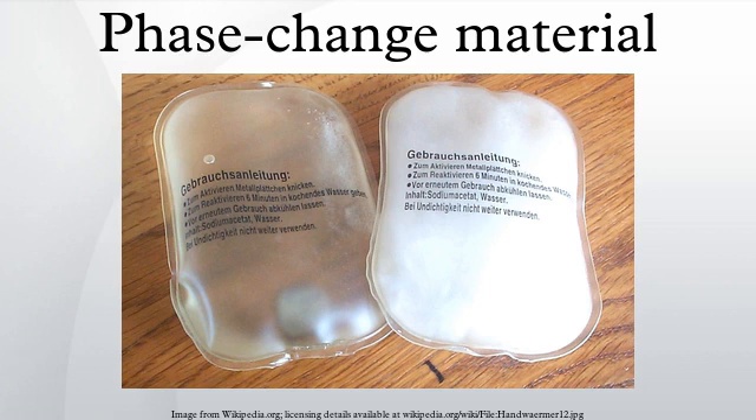Characteristics and classification. PCMs' latent heat storage can be achieved through solid-solid, solid-liquid, solid-gas and liquid-gas phase change. However, the only phase change used for PCMs is the solid-liquid change. Liquid-gas phase changes are not practical for use as thermal storage due to the large volumes or high pressures required to store the materials when in their gas phase. Solid-solid phase changes are typically very slow and have a rather low heat of transformation.